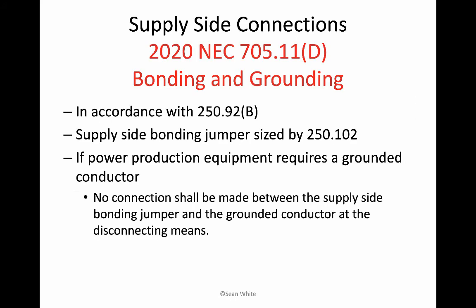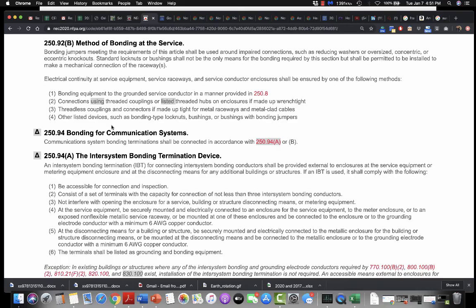When we talk about supply side connections, we're going to look at 705.11(D) for bonding and grounding with supply side connections, and that should be in accordance with 250.92(B). Let's take a look here. 250.92(B), method of bonding at service. Bonding jumpers meeting the requirements of this article shall be used around impaired connections such as reducing washers or oversized concentric or eccentric knockouts. Standard lock nuts or bushings shall not be the only means for bonding required by this section, but shall be permitted to make mechanical connections to the raceway.